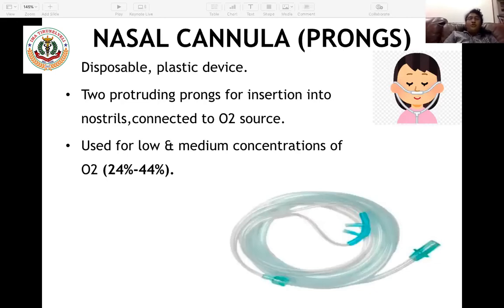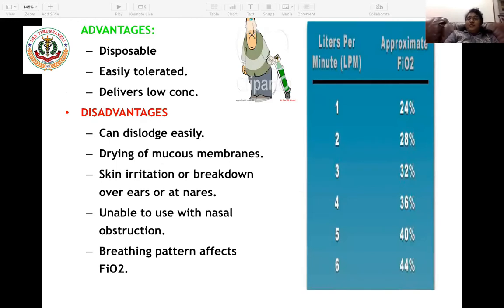This is the nasal cannula or nasal prongs. As you all know, this is a disposable plastic device with two nasal prongs which can be fitted into both nostrils. It provides 24 to 44% FiO2. We can give from 1 liter to 6 liters per minute, and 24% to 44% FiO2 can be achieved with the nasal prongs. The advantages are that it is disposable, easily tolerated, and delivers a low concentration.